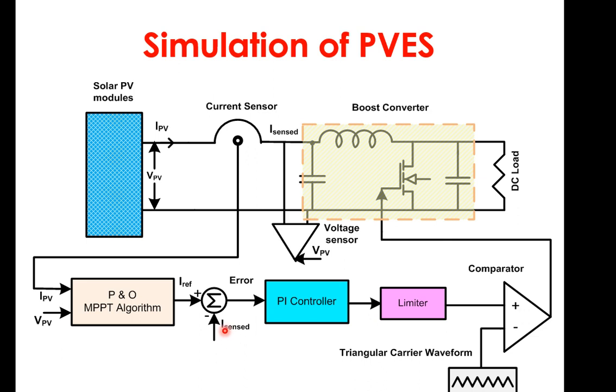If you take any photovoltaic module, this can be explained in another way, that it has a 20 volt and 4 ampere power supply, or 20 volt and 7 ampere power supply. So with the change in radiation, there is a huge impact, from 7 to 3.5, if I have half the radiation, from 1 sun to 0.5 sun, that is 1000 watt per meter square to 500 watt per meter square.